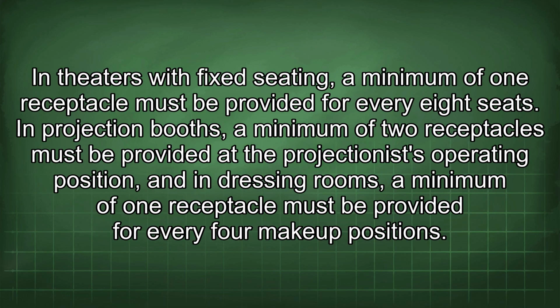In theatres with fixed seating, a minimum of 1 receptacle must be provided for every 8 seats. In projection booths, a minimum of 2 receptacles must be provided at the projectionist operating position, and in dressing rooms, a minimum of 1 receptacle must be provided for every 4 makeup positions.